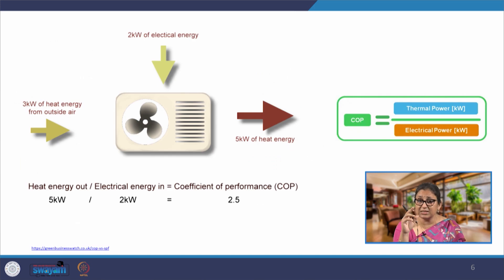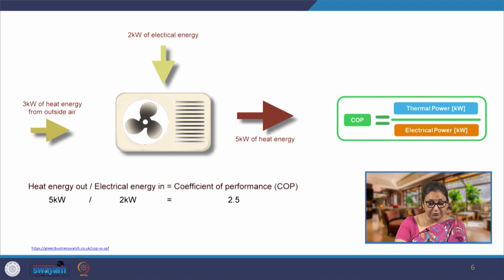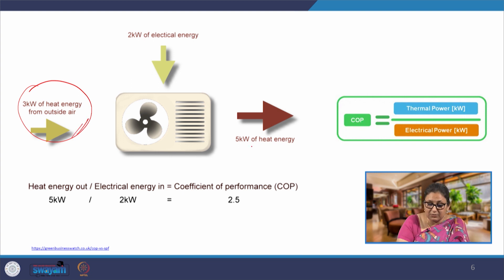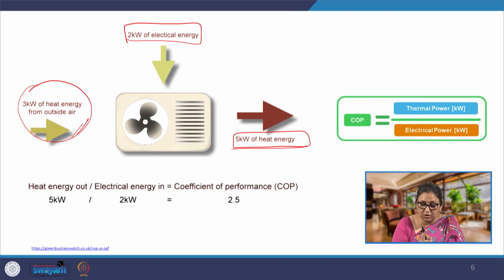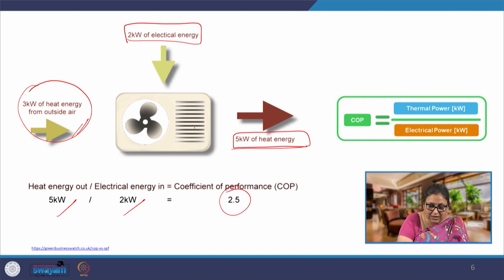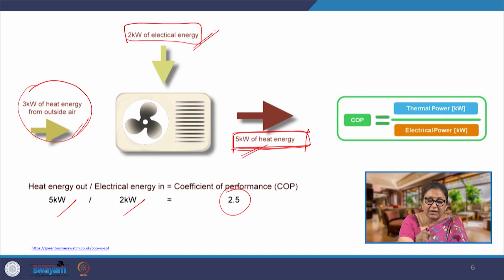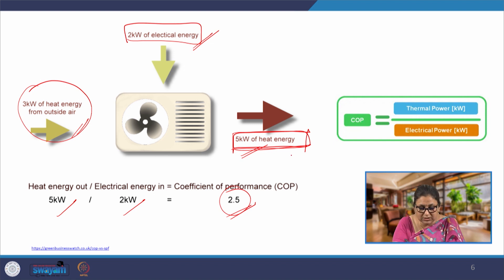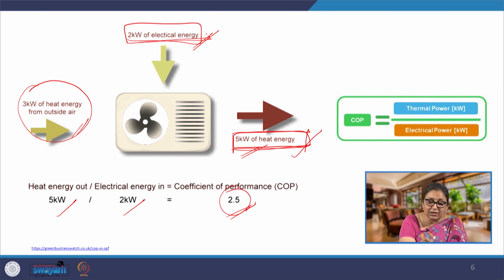To illustrate clearly: if we are removing 5 kW of heat energy overall by supplying approximately 2 kW of electrical energy (with 3 kW contributed from the outside air), the COP equals 5 kW divided by 2 kW, which is COP 2.5. This total work done in terms of energy extraction is 5 kW and the energy supplied is 2 kW. If any two of the three values are given, we can calculate the third — including how much energy will be consumed given the COP and the total work required.